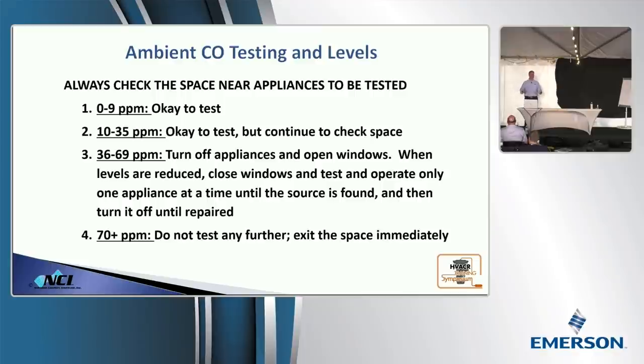How many of you guys in here own blower doors? Anybody? There's a great alternative use for a blower door. Ventilate CO out of the space. Clear it out. Then you can go back in and test. And you need to test each appliance one at a time to figure out where the problem is at. We're going to get into equipment testing here shortly. Once you find it out, you either shut it down or repair it. So you don't turn everything on all at once. You don't want to put yourself in harm's way.